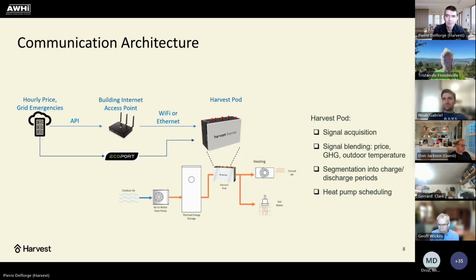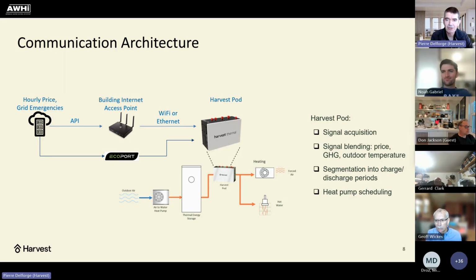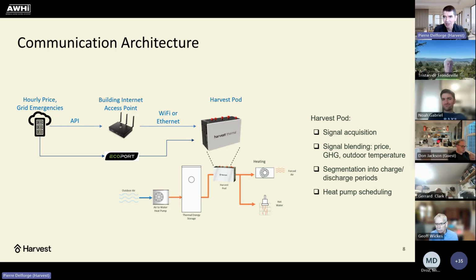Thanks. Maybe related to this is a soft start strategy. The SANCO2 doesn't have electric resistance, so it starts in heat pump mode, and you're only going to draw a kilowatt or so, a lot less than if you fire both elements. But there could be a way to soft start until you reconnect to the grid.